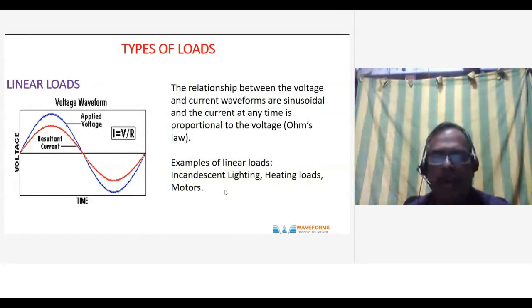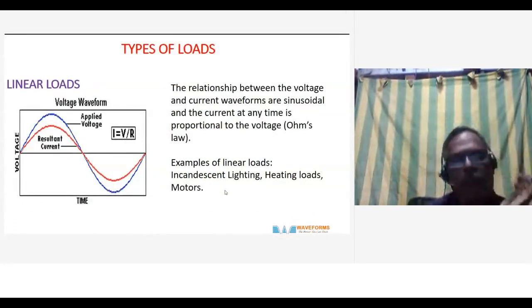There are two types of loads. One is the linear load. You can see that blue is the voltage waveform and the red is the current waveform. They are perfectly in sync, and they are continuous and proportional. The current waveform, which is the red waveform, is proportional to the voltage waveform. So it starts at 0 degrees, then peaks at 90 degrees, and then collapses to 0 degrees at 180 degrees. So this is the continuous periodic wave. This is an ideal waveform that any load would require. But you can find this only in a resistive load.